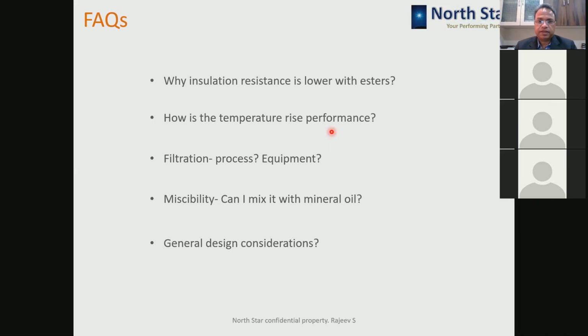Okay, how is the temperature rise performance? If you are doing nothing in your design and going for just replacing the liquid insulation with natural and synthetic ester in place of mineral oil in your new transformers also, then the temperature rise you will get is a little higher, depending upon the transformer rating and all. You can test the transformer up to 5 to 8 degrees centigrade more. If with mineral oil the transformer is giving you a temperature rise of, say, 45 degrees centigrade, then with ester it will test around 50 or 52 or about that value.